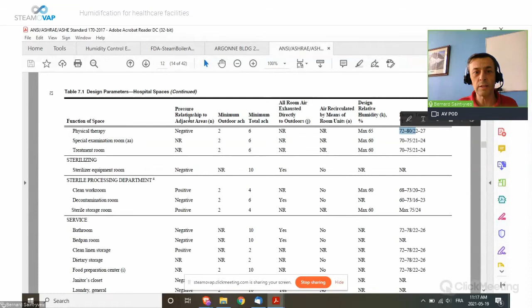I will try to rotate the view for you. So, let's say function of space, physical therapy: you should have a negative pressure room, a minimum of two outdoor air changes per hour, and the total air change per hour is 6, so it's 33% outdoor air minimum. No requirement for exhausting directly to outdoor, and no requirement for air recirculated. Humidity required is only a maximum, and here you have the temperature. So that's 7 parameters that ASHRAE is setting up for any function.